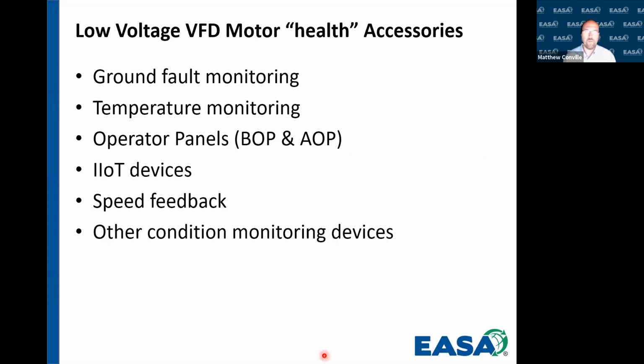When we want to monitor the health of the machine, we really want to look at a few different things. And we're not going to discuss all of these today in the interest of time, but we'll talk about some of the different things for you guys to think about. We can do ground fault monitoring, temperature monitoring. We can have operator panels on the drive panel that will help us understand what's going on. We can use some of these IIoT devices. A lot of these are able to integrate into the drive system as well. You can do speed feedback, which we already talked about. And we can even do other condition monitoring devices, such as airflow, and in some instances, even vibration, just to name a few.